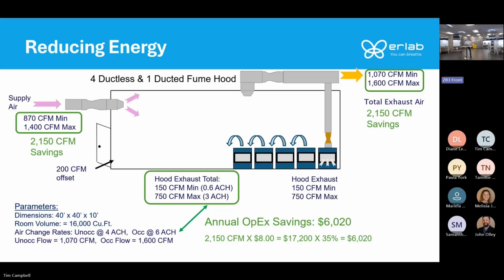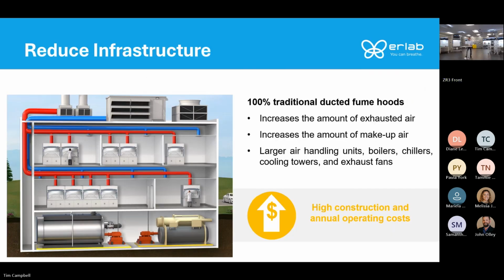They're independent systems that are basically recirculating air within the space. The chemical vapors are pulled away from the user, pulled up in the filtration column, and clean air is returned back into the lab space. So you don't need extra air. You don't need to overventilate it. You can keep your air change rate at what the hazard risk analysis prescribes.